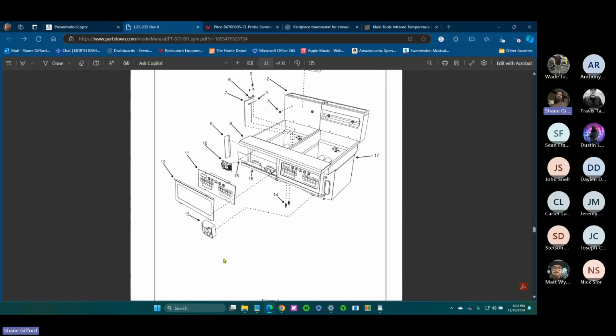Because when you're running all of your gas appliances off that one line, let's say hypothetically there's one gas meter outside and that feeds all of the cooking appliances. Well, in order to get a true reading on how pressurized your line is, your line might be pressurized at 14 inches of water column or 10 inches water column, but then you go to fire on your biggest appliance and all of a sudden, now your inlet pressure just dropped like big time, right?